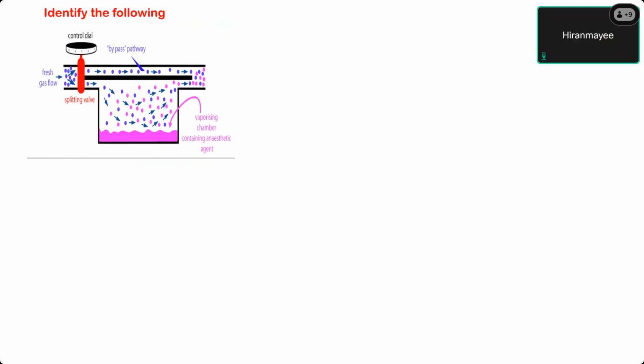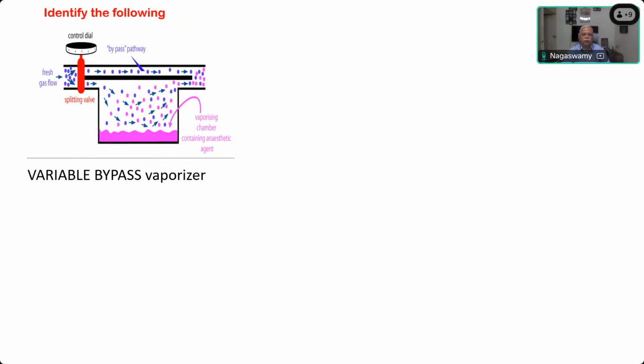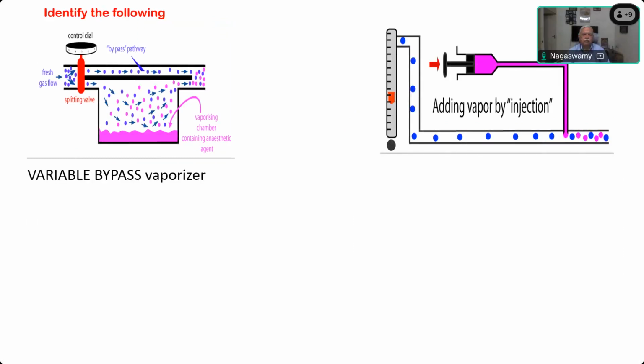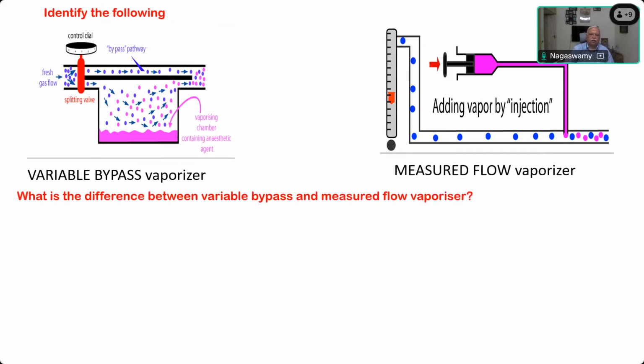Variable bypass vaporizers. Variable bypass vaporizer. Very good. Injectable type of vaporizer. Direct injectable vaporizing agent. With the correct terminology? Injection type of vaporization, called measured flow vaporizer. Okay. So this is variable, this is measured flow. What is the difference between variable bypass and measured flow vaporizer?